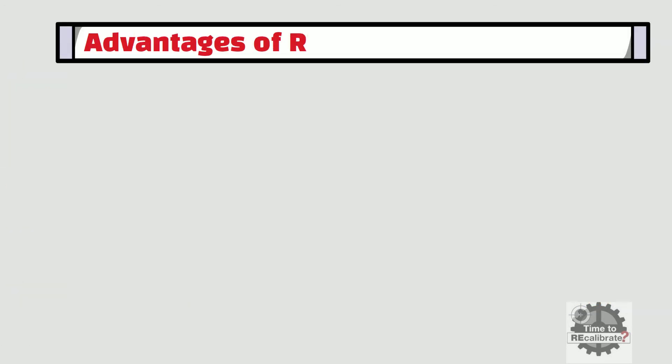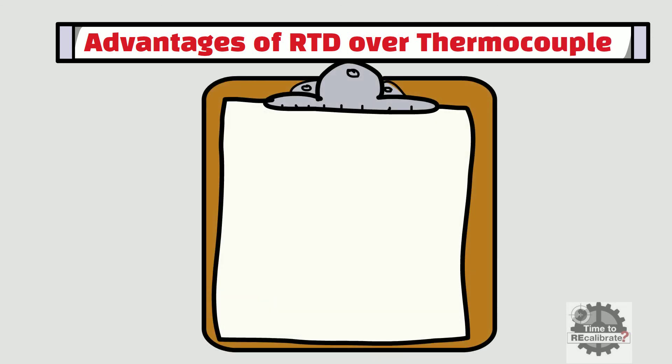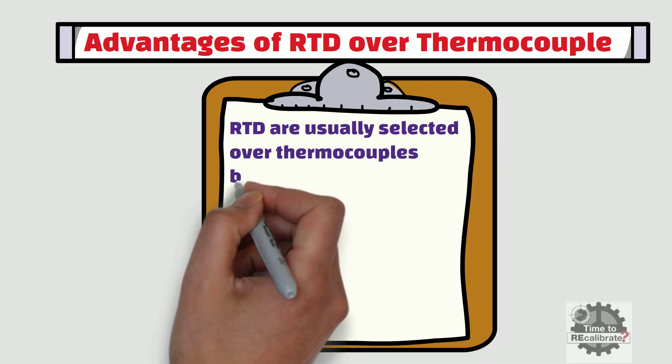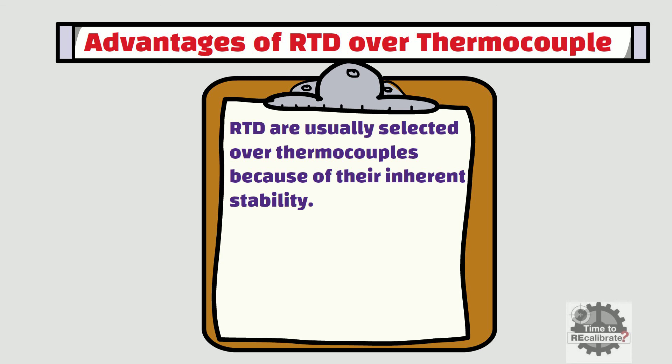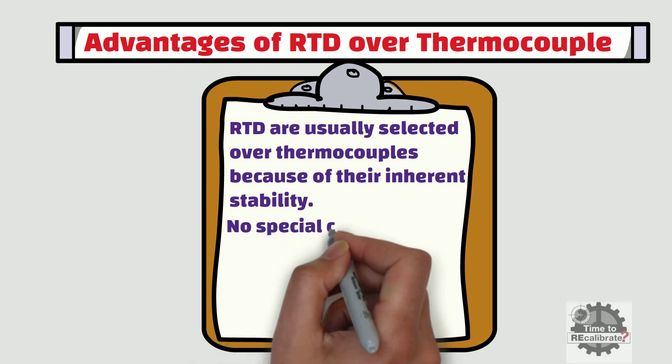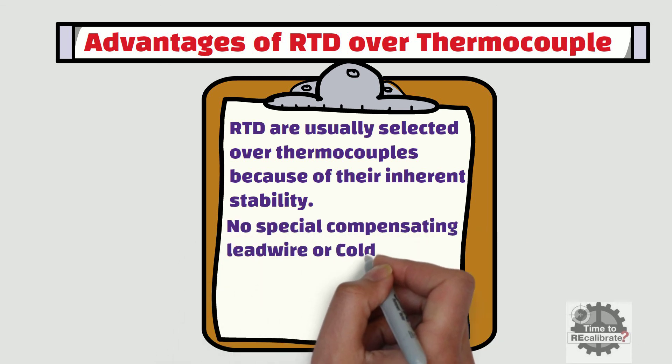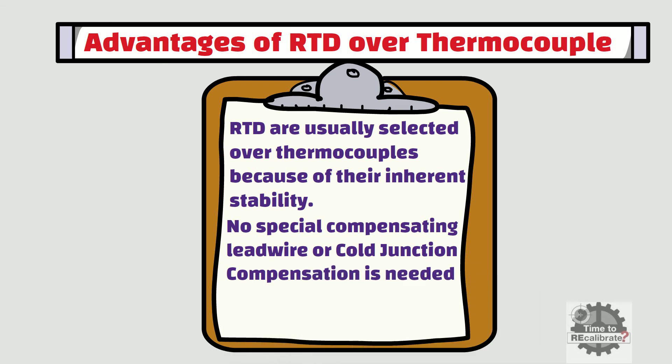Now let's learn the advantages of RTD over thermocouple. RTDs are usually selected over thermocouples because of their inherent stability. Another advantage over thermocouples is that no special compensating lead wire or cold junction compensation is needed for RTD.